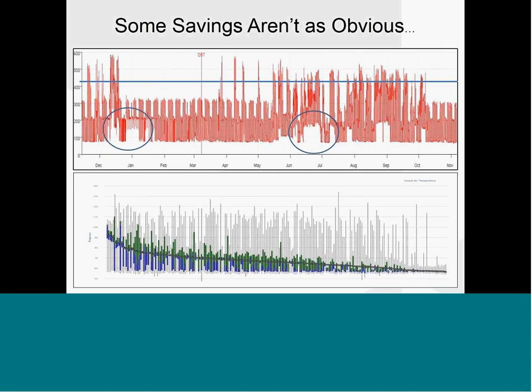What I want to point out here is those two circles at the bottom of that chart—those are the savings that aren't as obvious. Some of our guys noticed that when looking at this information. That tells us that some equipment which should be setting back and shouldn't be running at certain periods is running for some reason. Those are areas to target. You can see it's not even seasonal—one circle is in January, the other's in July. If it were seasonal you'd expect that pattern, but in this case it's not.